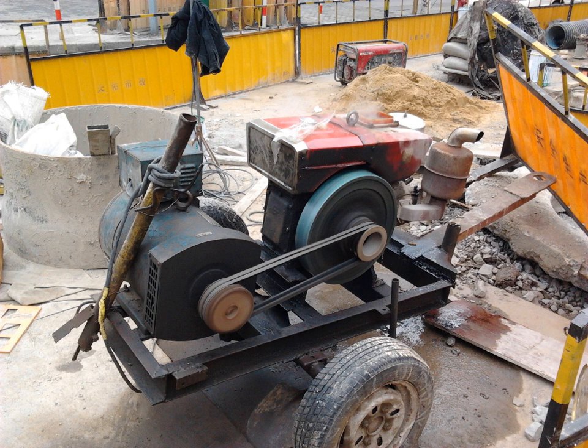Topic: Safety. Every year, incorrectly used portable generators result in deaths from carbon monoxide poisoning. A 5.5 kilowatts portable generator will generate the same amount of carbon monoxide as six cars, which can quickly build up to fatal levels if the generator has been placed indoors.